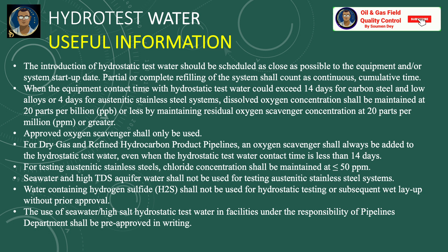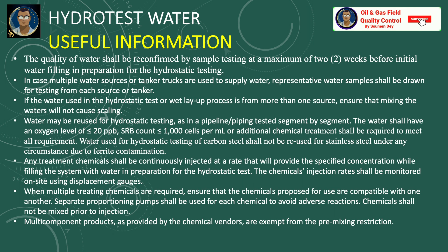The use of seawater or high-salt hydrostatic test water in facilities under the responsibility of the pipelines department shall be pre-approved in writing. Note that these are examples from a specific area and may differ based on country requirements or local and international standards adopted for the project. The quality of water shall be reconfirmed by sample testing at a maximum of two weeks before the initial water filling. In case of multiple water sources or tanker trucks are used to supply water, representative water samples shall be drawn for testing from each source or tanker.